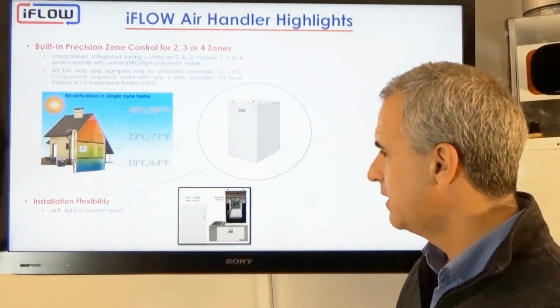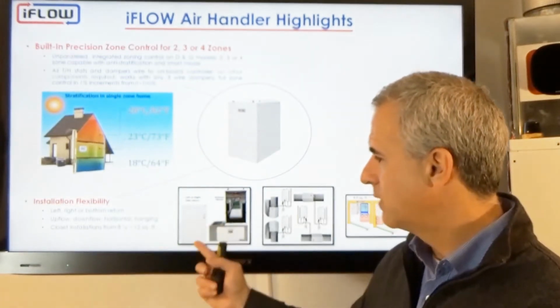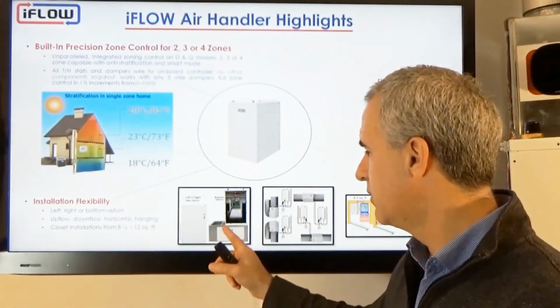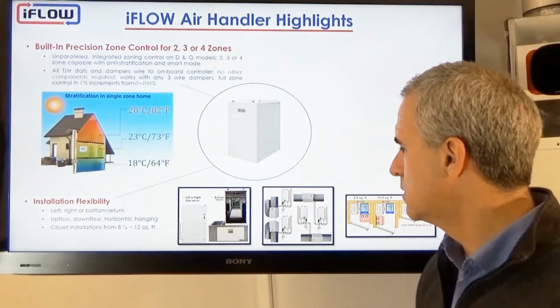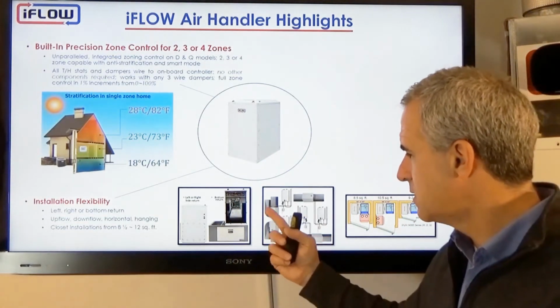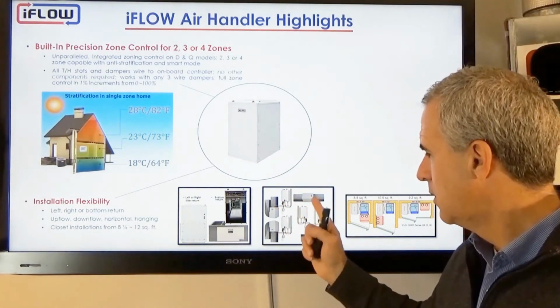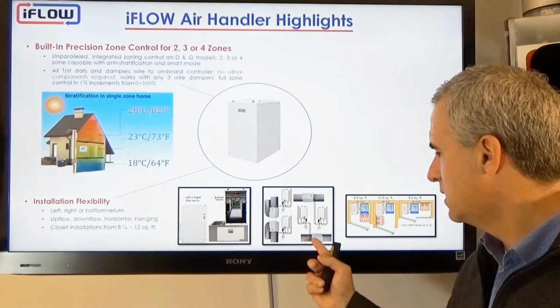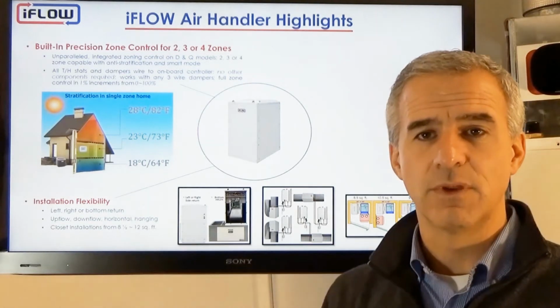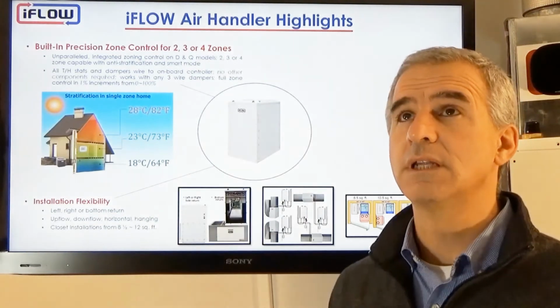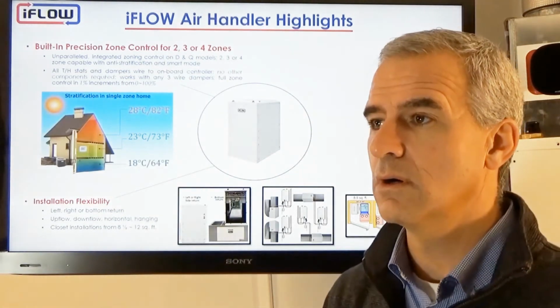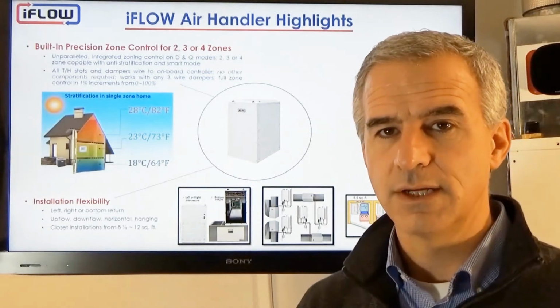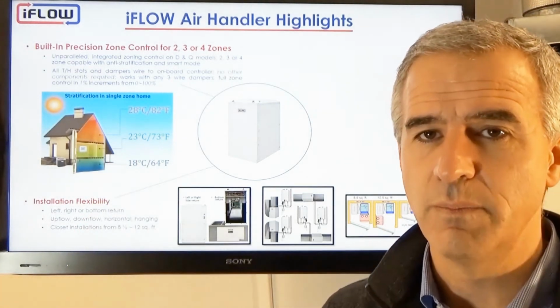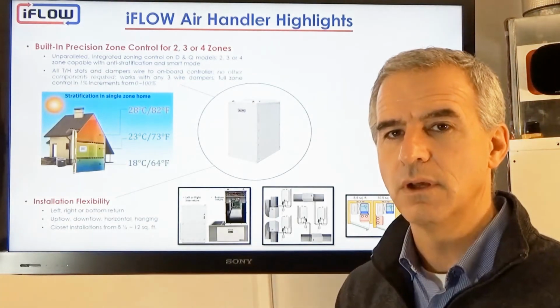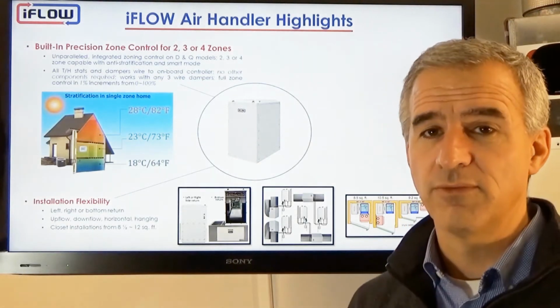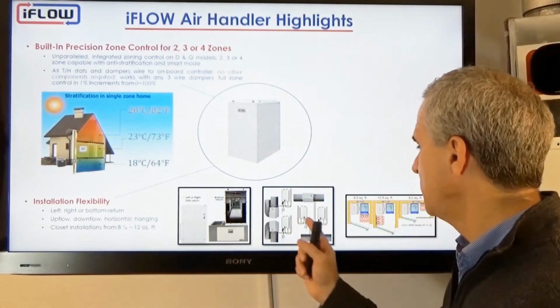In terms of installation, we give you lots of flexibility. You can bring the return duct on the left side, the right side, or even on the bottom. So 3 ways to bring the return duct. We can install this unit upflow, downflow. We can go horizontally above, horizontally below, or we can even hang it from the rafters. So if you have ceiling trusses or joists, then we can actually strap the unit, because it only weighs 63 pounds, from 63 to 93 depending on the unit. But we can strap it from the ceiling to open up floor space, so if you're in a tight mechanical room. So lots of flexibility that way.